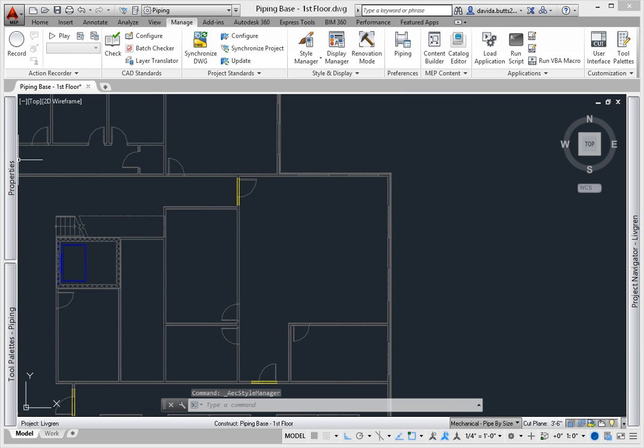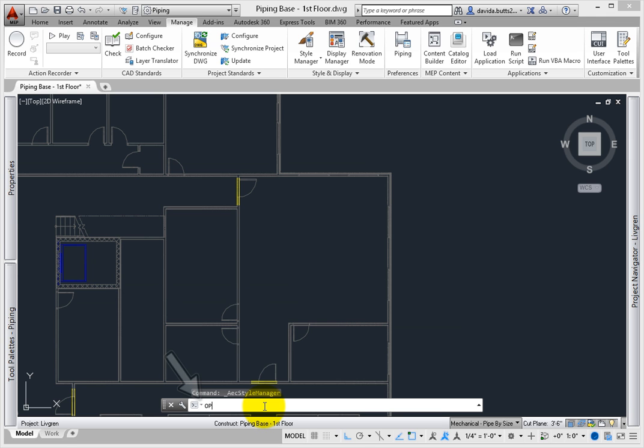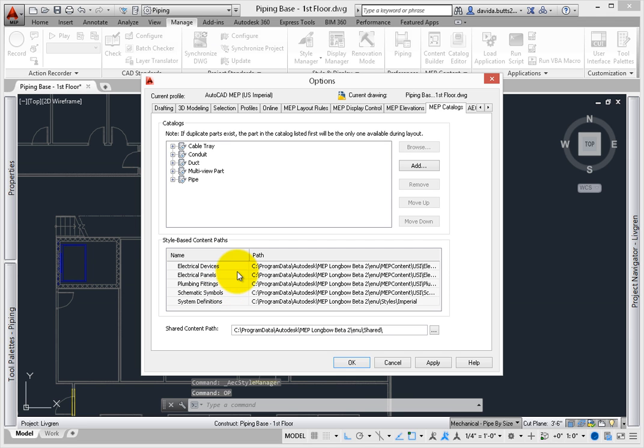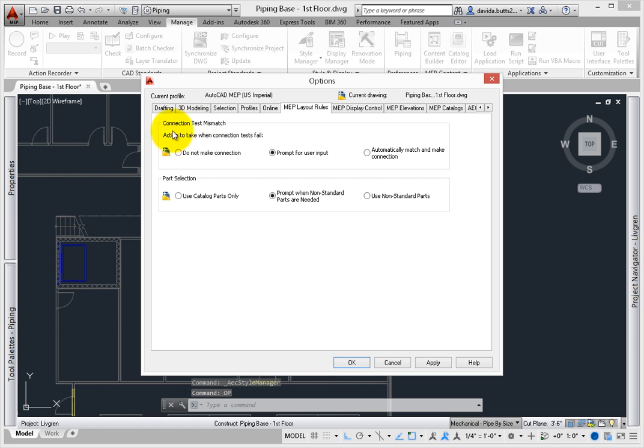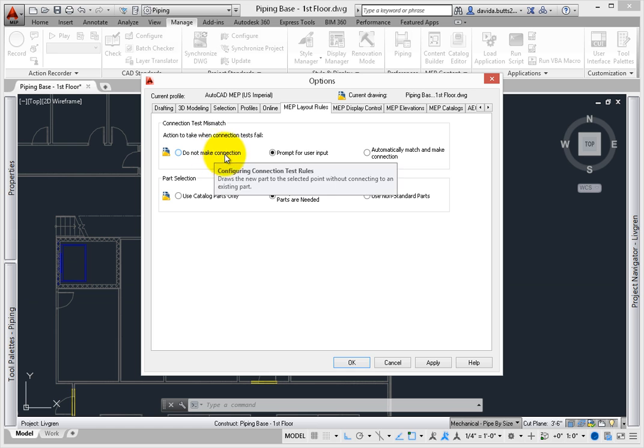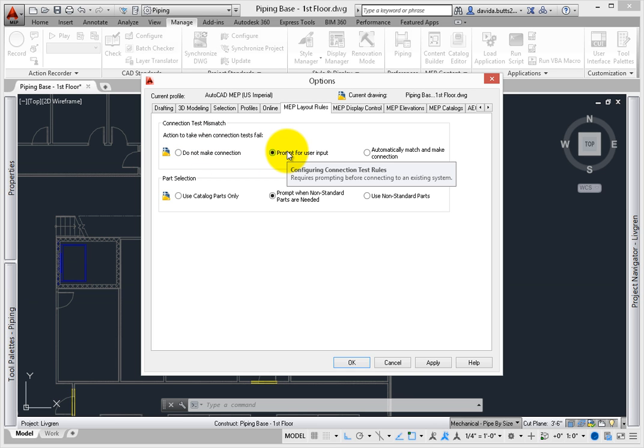Next, check the options. Before you create any pipe, you need to check some items. Type in OP on the command line and press enter. Scroll to the MEP tabs. Remember the system group? On the MEP layout rule tab, there is a connection test mismatch setting. By default, AutoCAD MEP will ask before it lets you connect systems that belong to two different groups. Leave this set to prompt for user input.